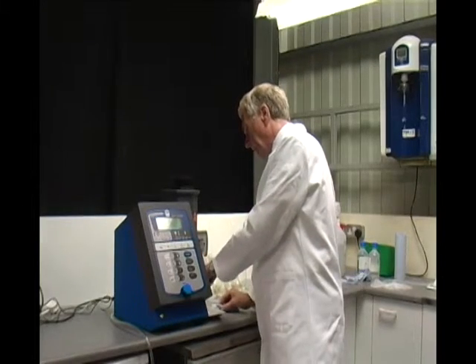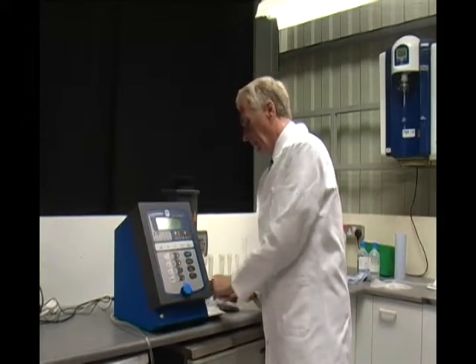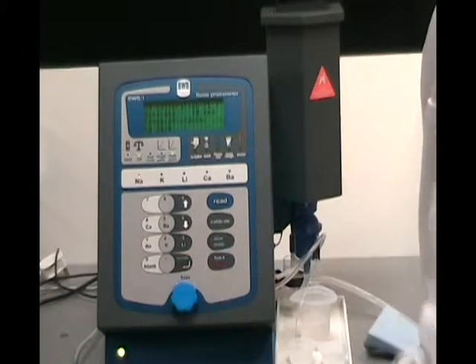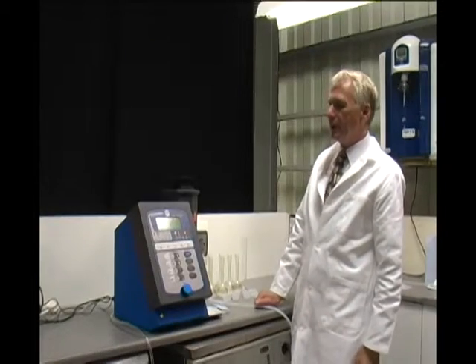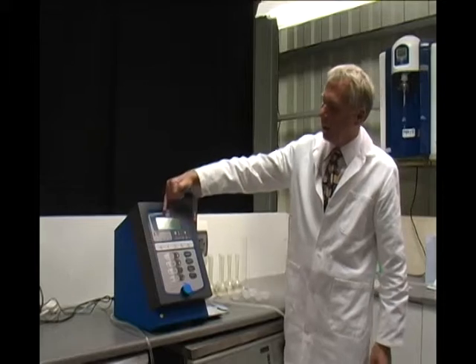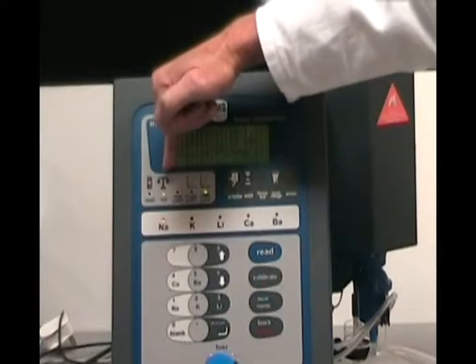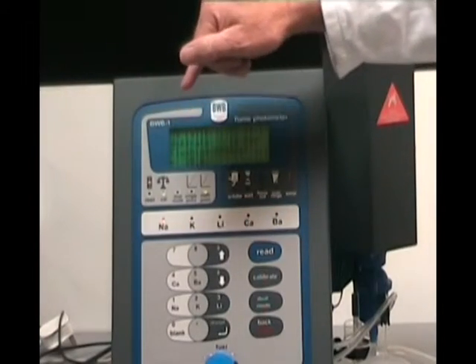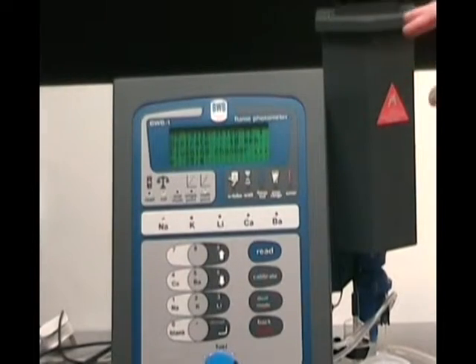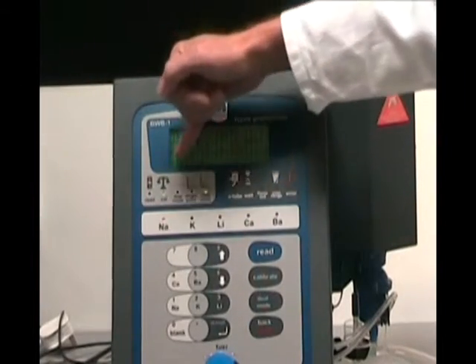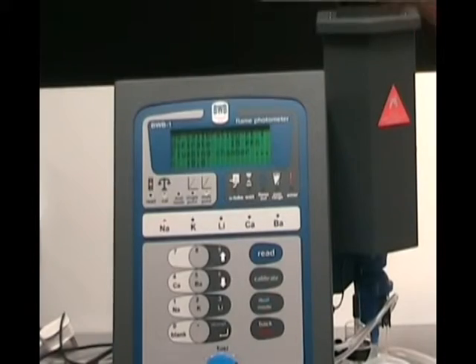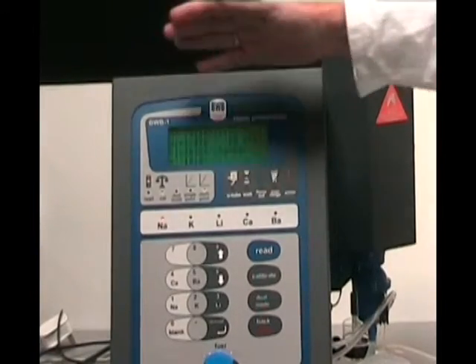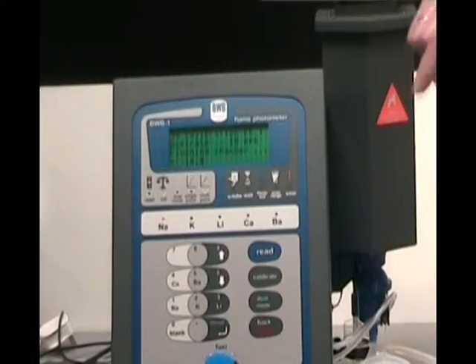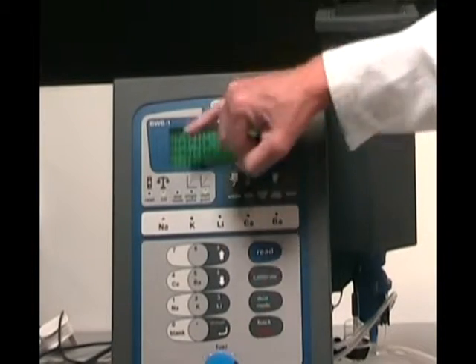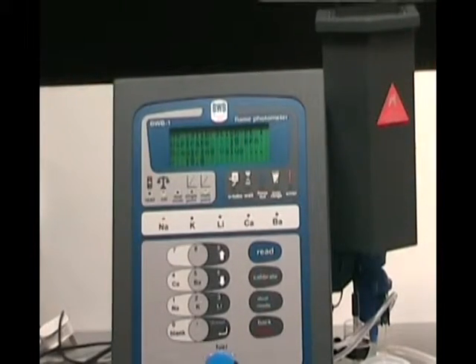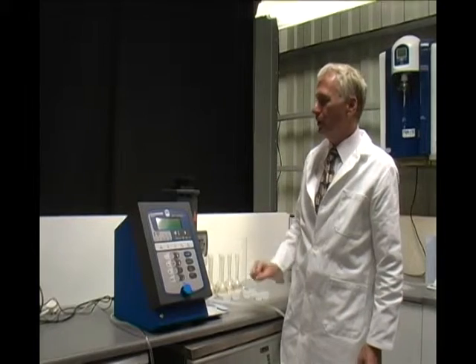So I now put my aspiration tube into my 10 ppm solution and press accept. Once again it says flushing chamber, and coming back to these two icons, the first one is a graphical representation of the value of the reading, and the second one is a representation of the noise within the system. So ideally you want the first one as being a straight horizontal line and the second one as being a single dot, meaning that there is very little noise within the system.